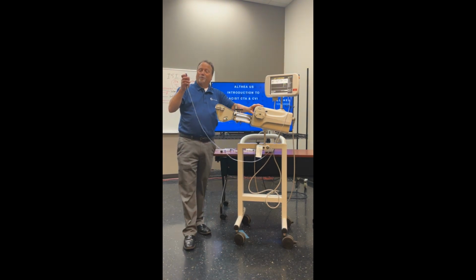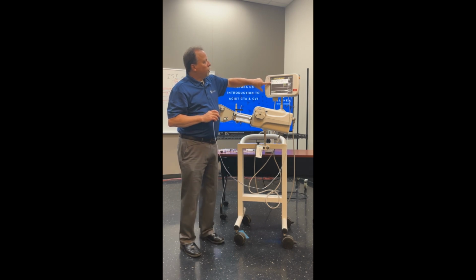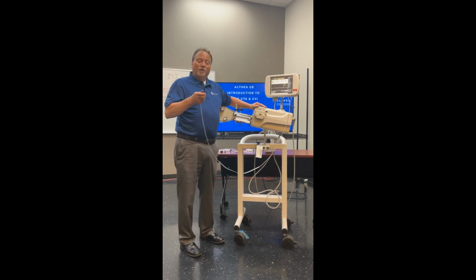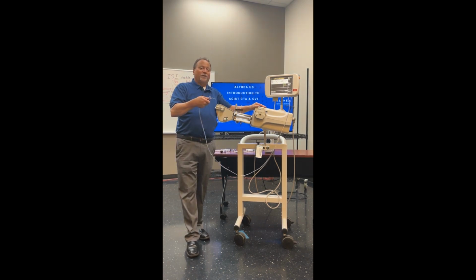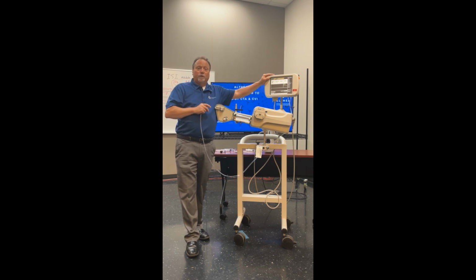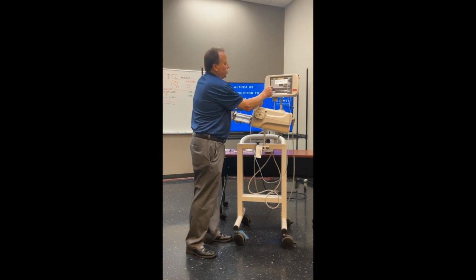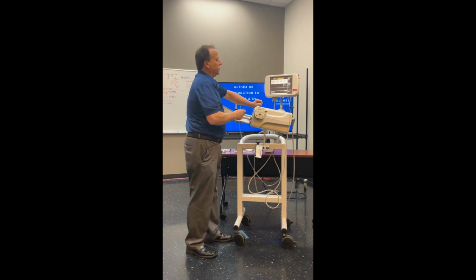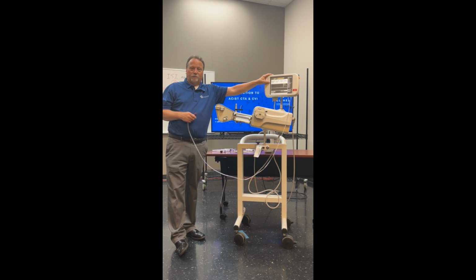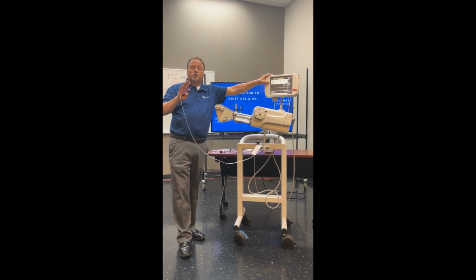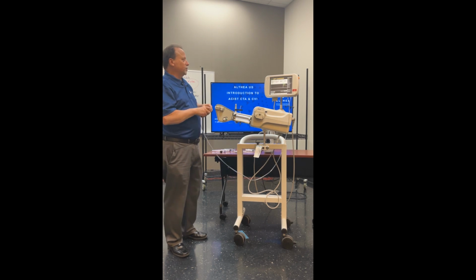So now the hand controller is calibrated. Even though in our protocol our flow is 4 milliliters per second, we can actually vary the flow rate just by the pressure of our thumb, soft or hard, and the flow rate will go up and down, but will never go past 4, or our programmed flow rate. So if I go in and program it to, let's say, 10, it will never go above 10 milliliters per second. So the operator can slow down the flow rate or speed it up just by the controller. Some of the cardiologists love that feature. They just love it, and they love this injector because of this feature.